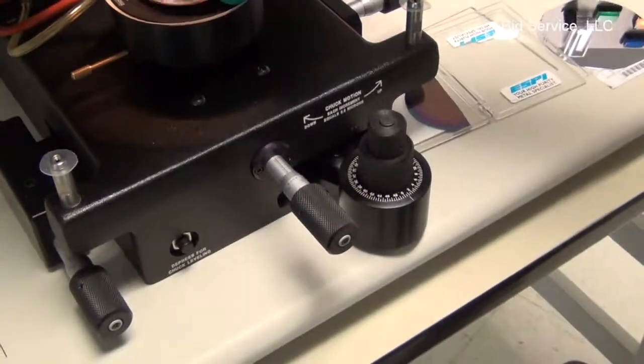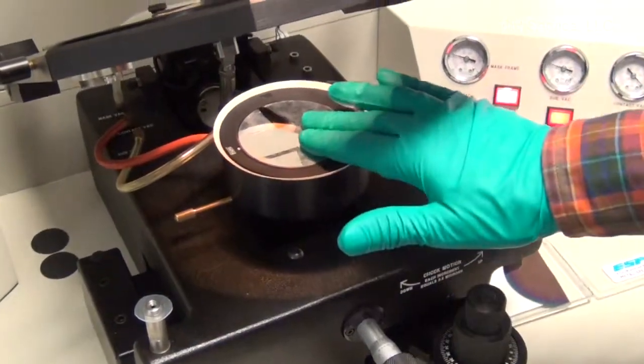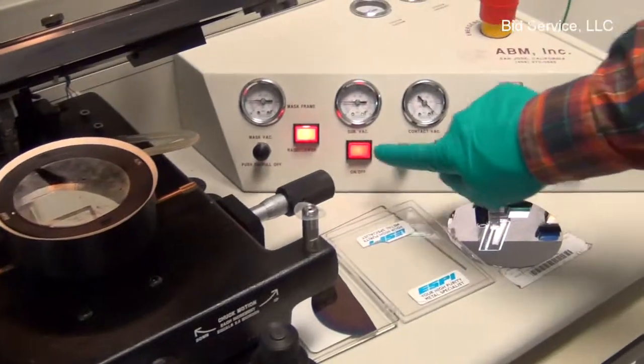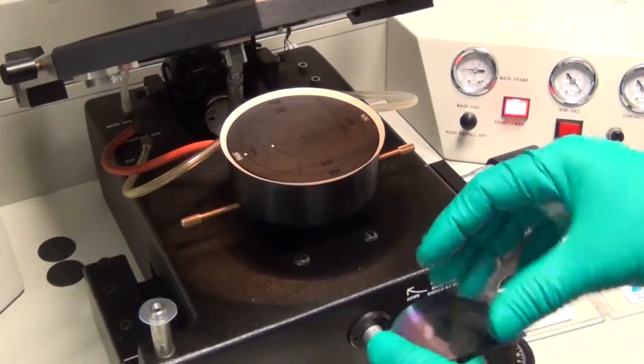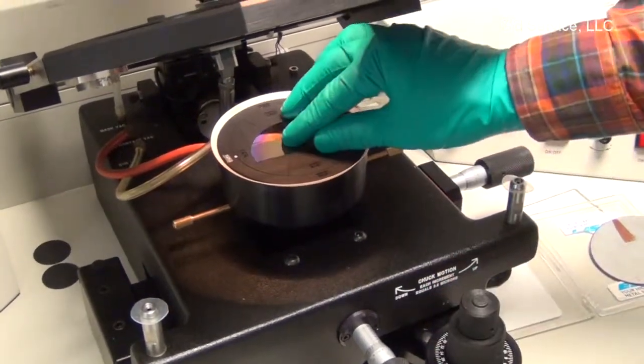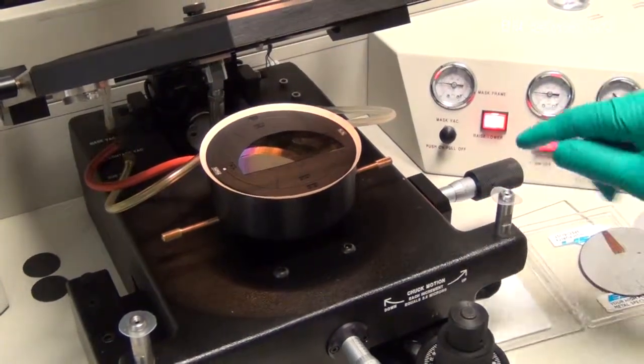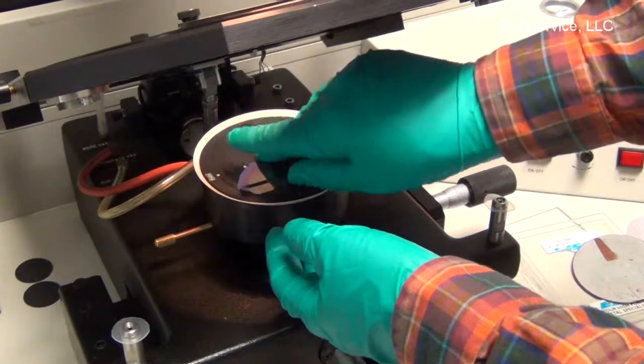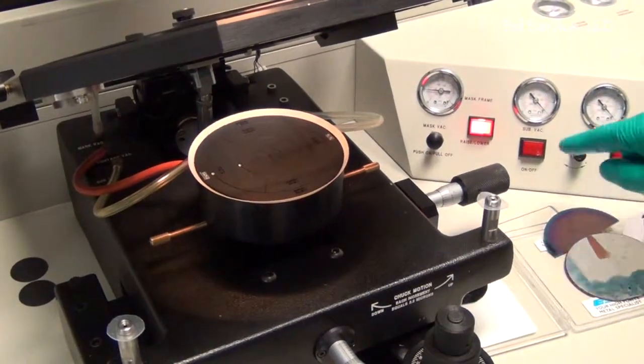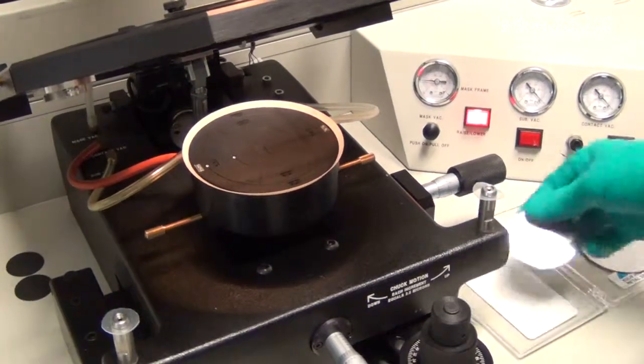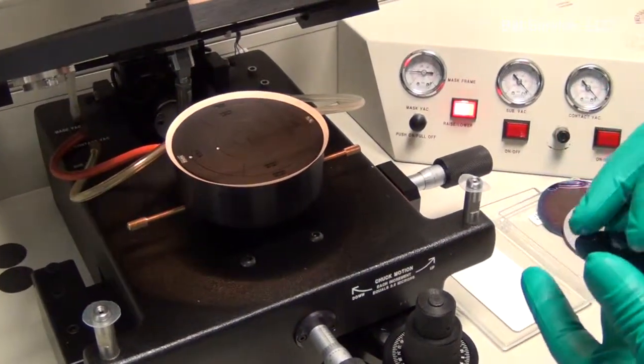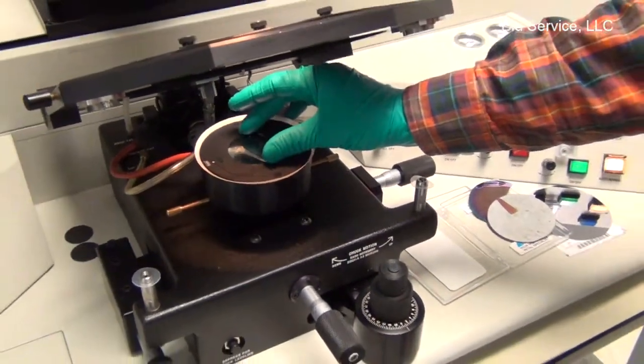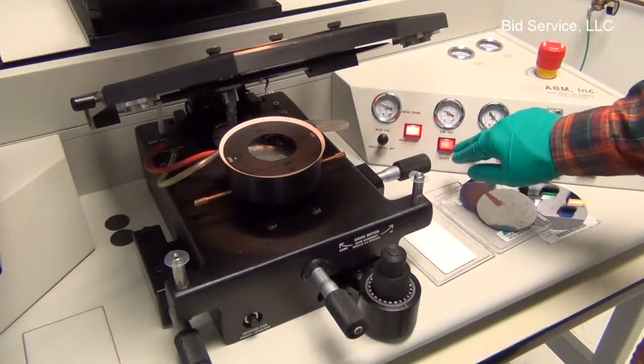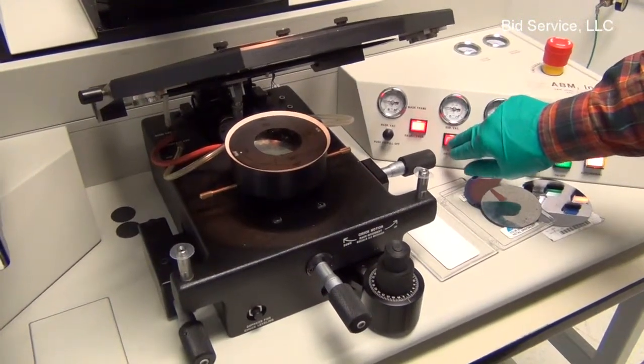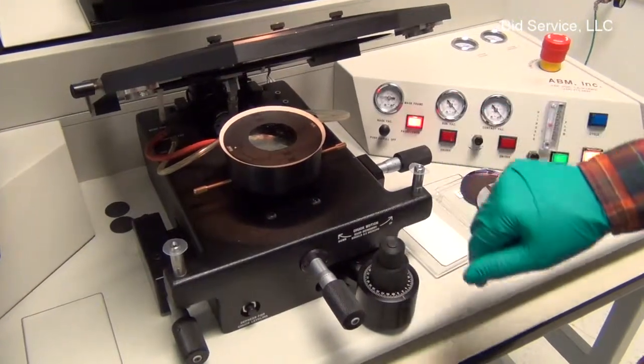The substrate holder can also handle 3-inch wafers. I can get the full vacuum level at 25 inches by turning on the substrate vacuum. And here's a section of a 3-inch wafer. You can also use a section of a wafer. In order to keep the substrate parallel to the mask, the smaller than 4-inch wafer pieces have to be placed approximately at the center of the chuck. Otherwise, it will cause problems by creating a wedge gap between the substrate and the mask.